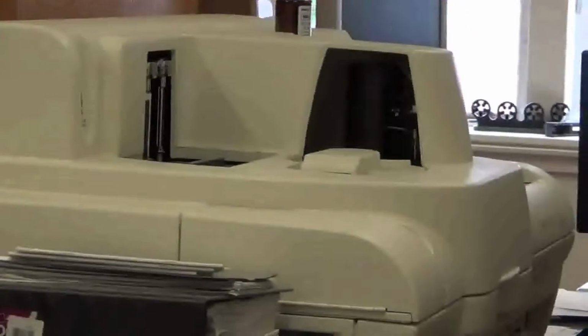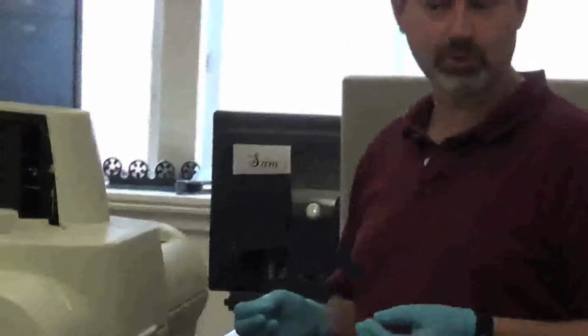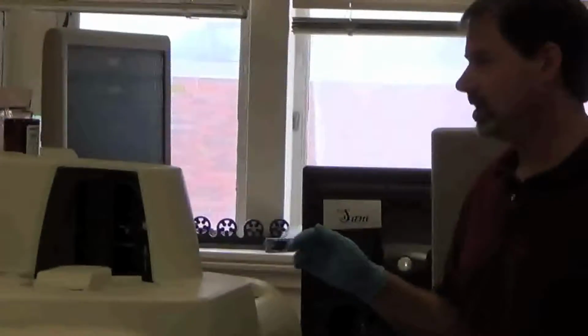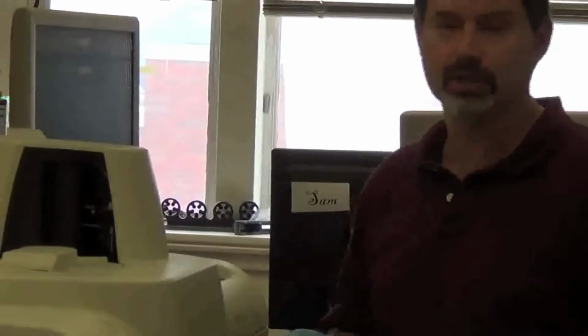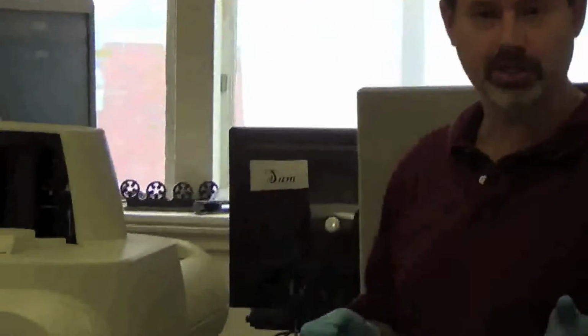This is the Immulite 1000. It's a chemiluminescence analyzer that we're able to measure multiple different hormone levels in and compare to standard controls, which are generally based on human control values, but we've extrapolated into using it for animal use too. To run this machine, we have to calibrate on a regular basis, definitely before each run, so that we can see that the standards are actually functioning well, so we know our values are going to be correct.